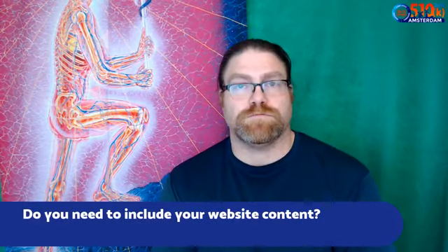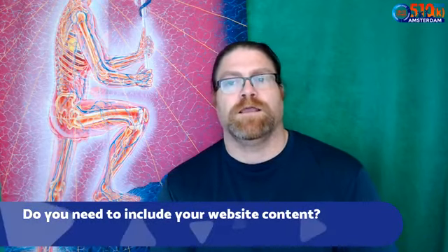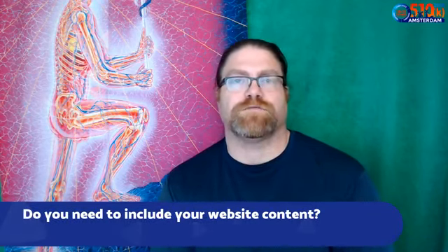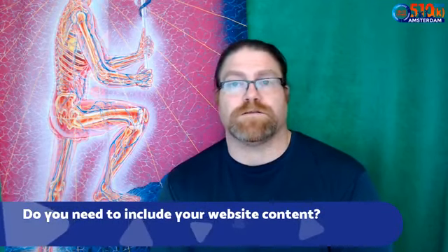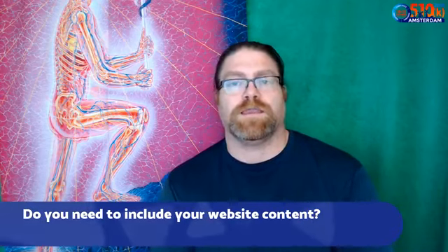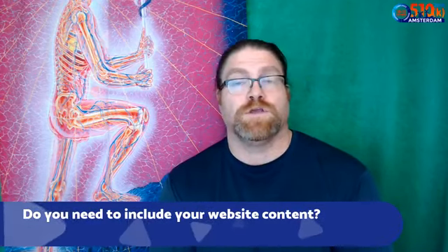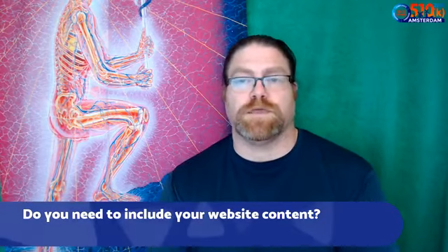But one thing you should be aware of is the FDA will look at your website. So even if you don't submit the website content, and even if it's European only, the FDA is still going to look at that, and they're going to look for things that you can't have, and they're going to ask you to address those, remove things that are unacceptable, or clearly differentiate this is for Europe only, and here's the website we created for US only. So you might want to address that question up front to make sure your submission review goes smoothly.